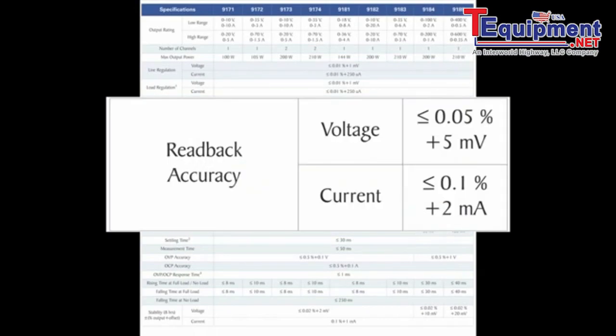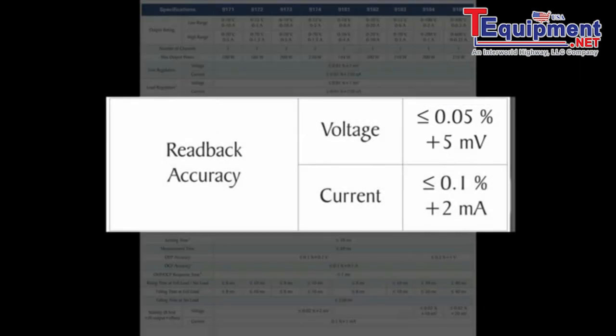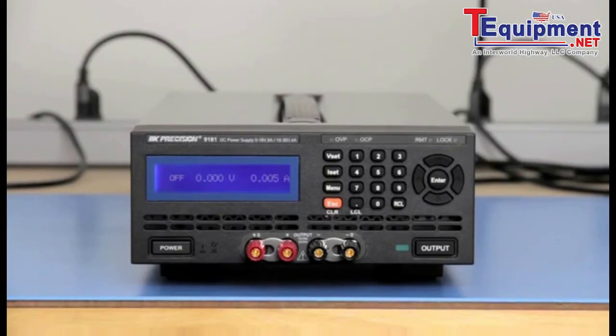Its readback accuracy is specified as less than 0.05% plus 5 mV, and less than 0.1% plus 2 mA. The programming or setting accuracy determines how close the set voltage and current values are to the actual value. It is expressed as a percentage of the setting plus offset.